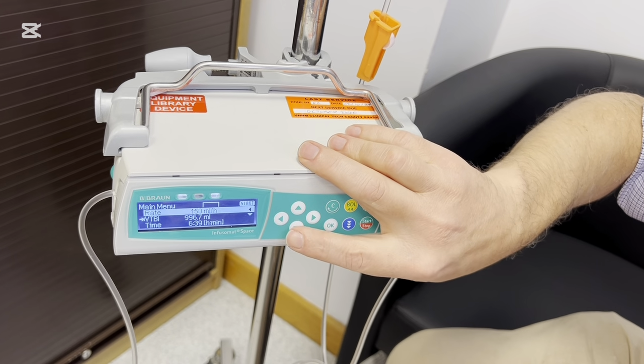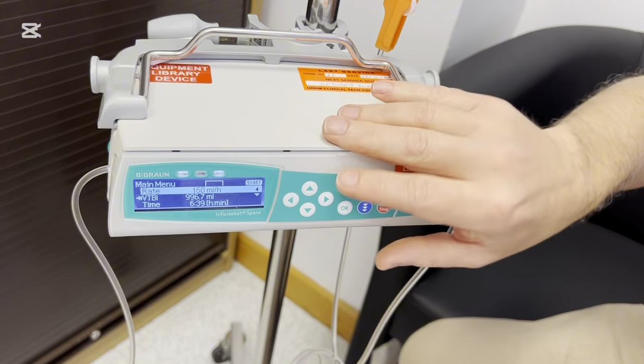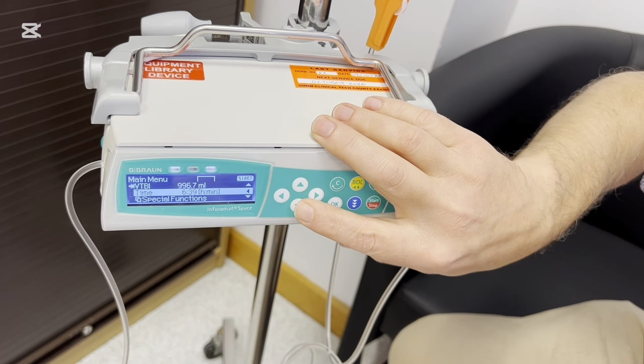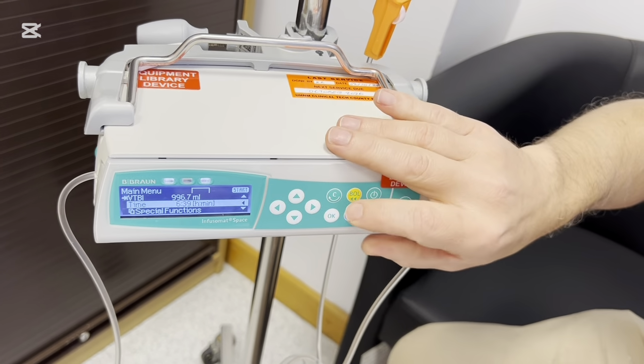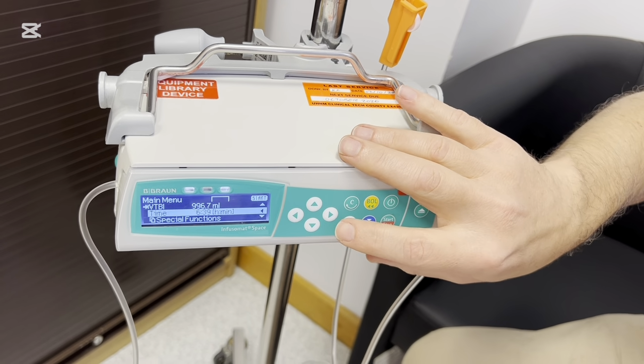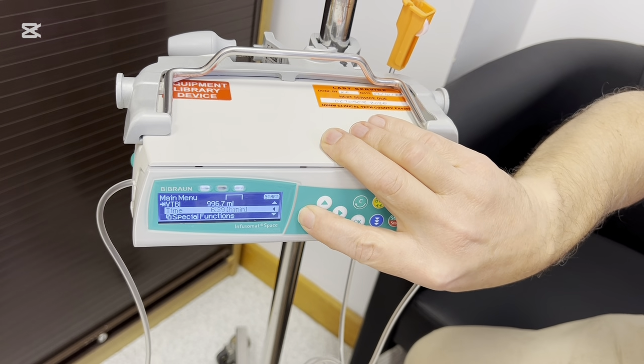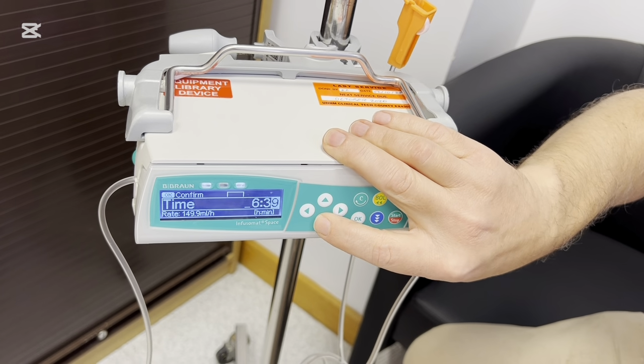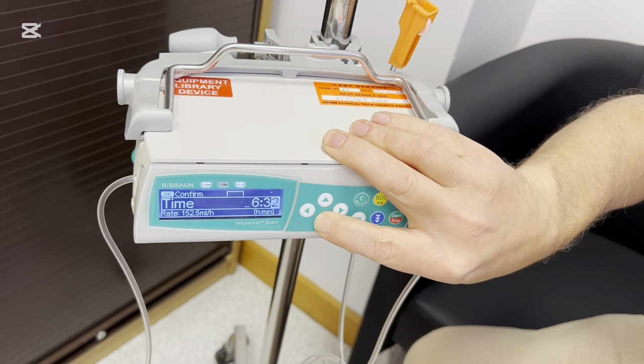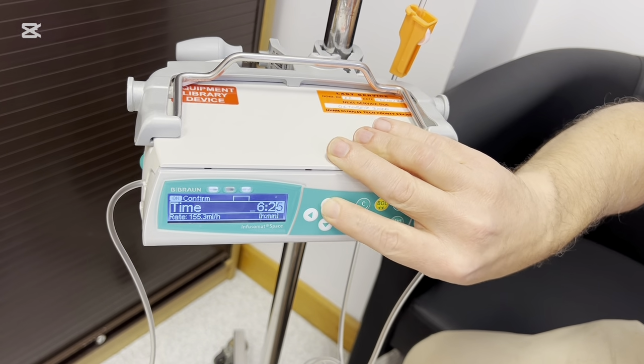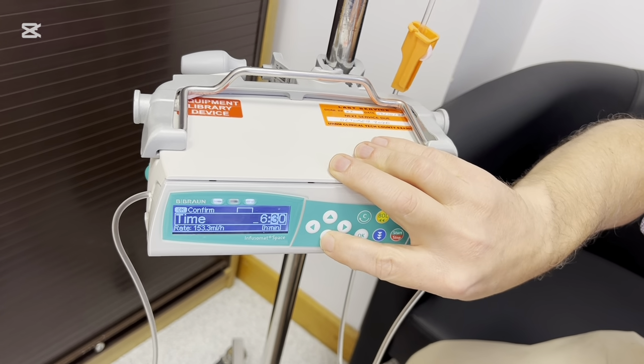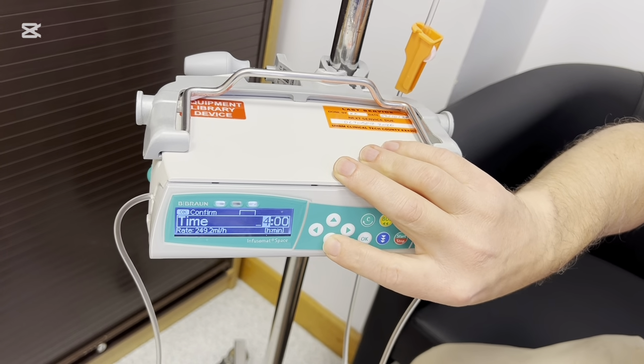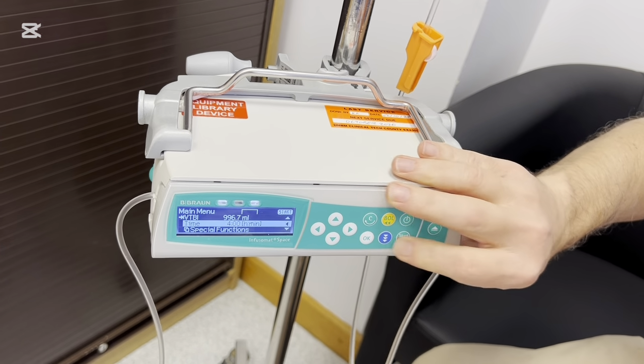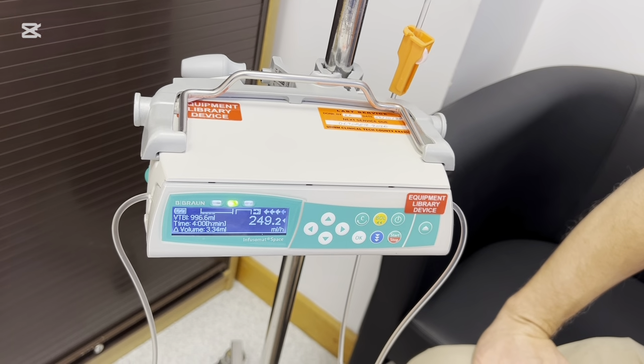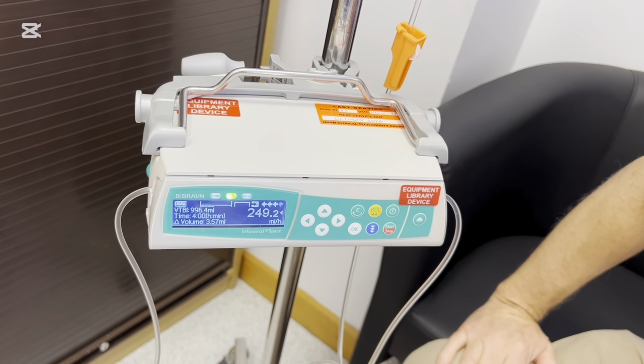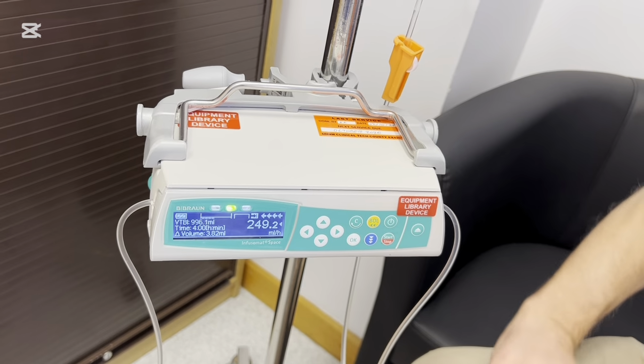We talked about different ways in which you can select how to administer the fluid. So we've selected mils per hour. Another way of selecting it is over time. So the pump still thinks it's delivering 996 mils of fluid. So we can change, rather than delivering it over at 125 mils an hour, we can say we want a litre perhaps over 4 hours. If we start it now, it's recalculated the rate to 249.2 mils an hour because we already used some of the fluid within the bag.